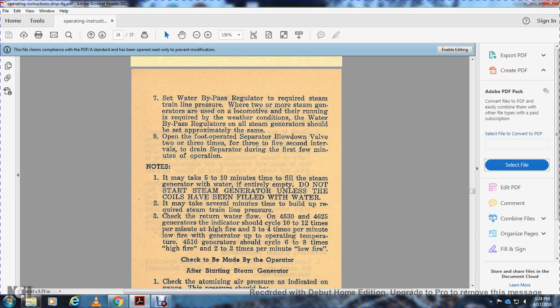3. Check the return water flow on the 4530 and the 4625. The indicator should cycle 10 to 12 times per minute on high fire and 3 to 4 times per minute on low fire. With the generator at operating temperature, the 4516 generator should cycle 6 to 8 times on high fire and 2 to 3 times on low fire.